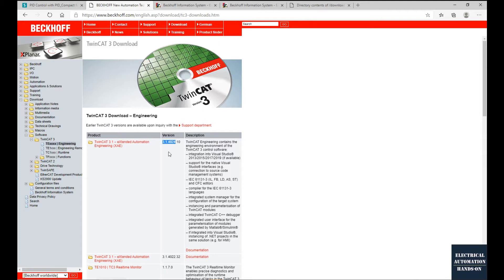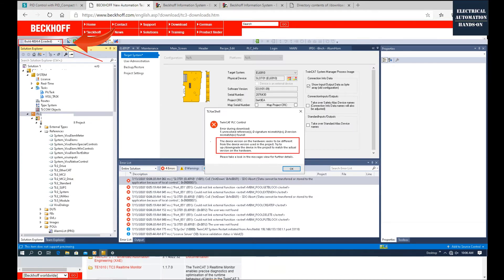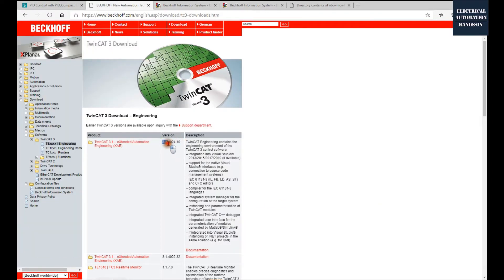Similarly, if the TwinCAT 3 controller's internal version is 3.1 4022 and you have installed the latest TwinCAT 3 4024, when you try to download to the controller the system will pop up an error showing: 'The device's version on the hardware seems to be different from the device's version used in the project. Try to upload and downgrade the devices in the project to match the actual version of the hardware.' So we need to match the main version — 3.1 4024 — these digits are very important.